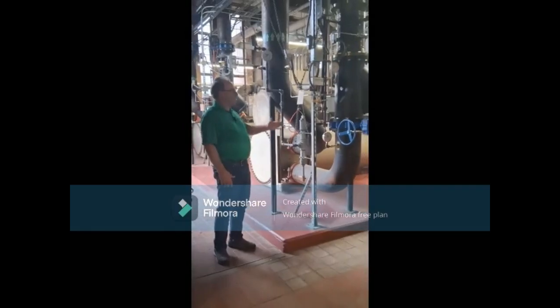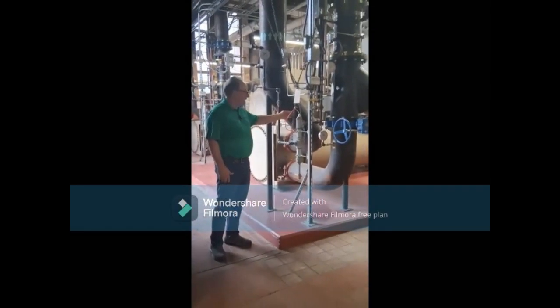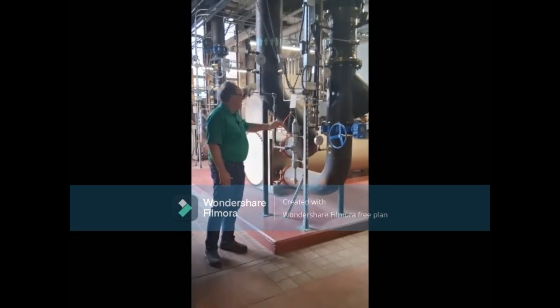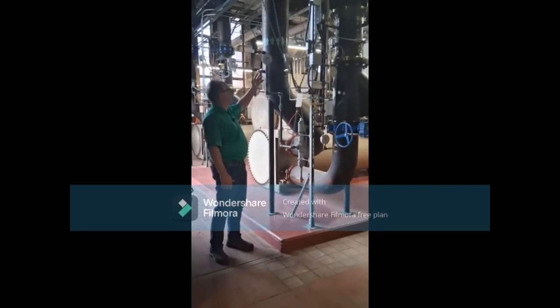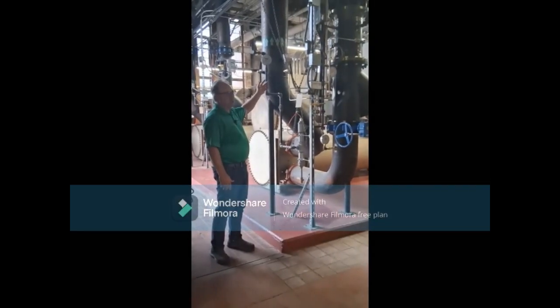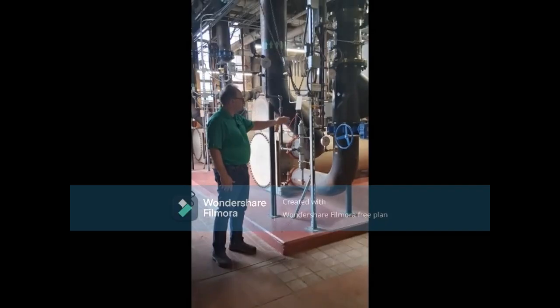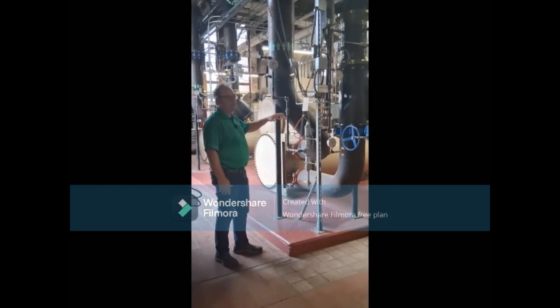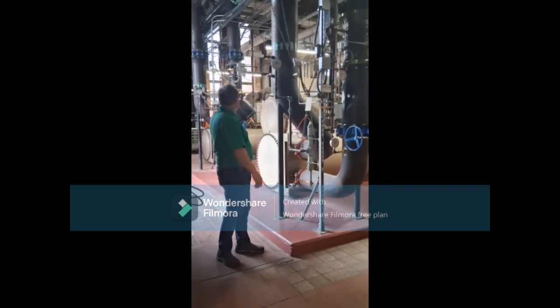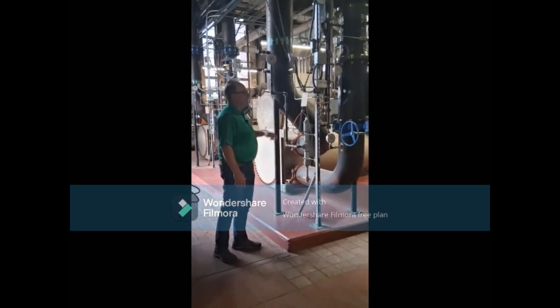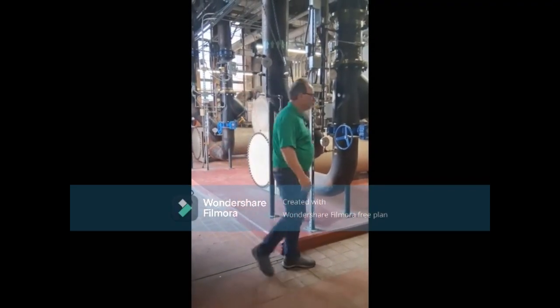So this is chiller 2, the same setup as chiller 1. You got the galvanic cell and the probe here. It sees the water going from the condenser water return and supply through this probe system, pulls out the positive energy in the water, goes to the control panel, back to here, and follow me.